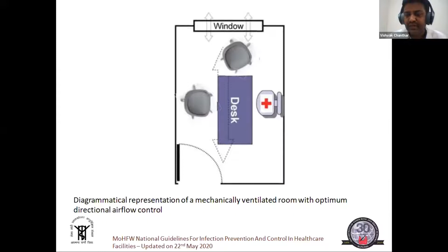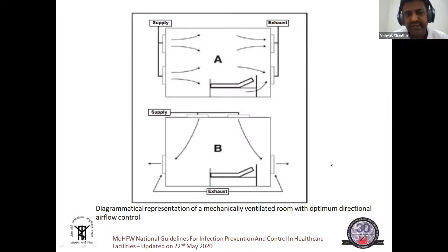And this is the arrangement of a ventilated room in an IP setting. We have our supply from the roof, so it's recommended to place an exhaust on the side of the walls so that this room is mechanically well ventilated, as per the recommendation of the Ministry of Health and Family Welfare.